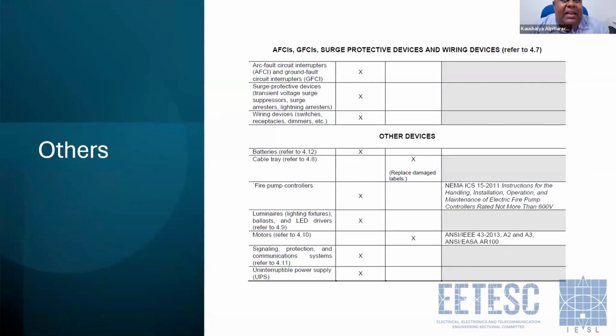Others, all the electronic interrupters, protective devices, GFCIs, metering, and all, you have to replace. Especially batteries. Cable trays you can use if not severely damaged. Fire pump controllers, lighting, ballast, LED drivers, motors: smaller motors are better replaced, but larger motors, yes, you can condition and reuse. Signaling, protection, communication systems, UPSs.